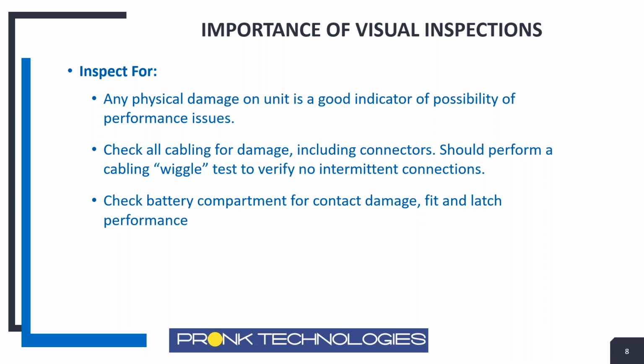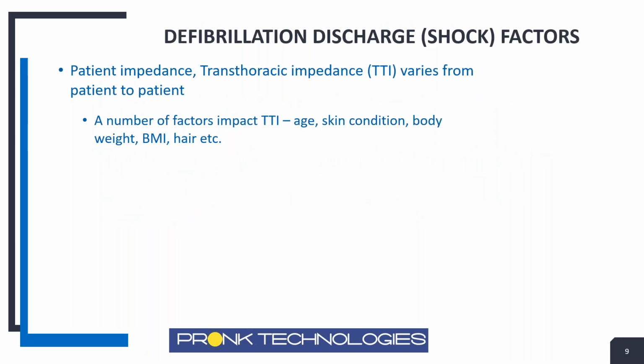It works once, but they would vibrate the unit a little bit and the battery would lose contact, the defibrillator would turn off, or the latches were damaged in some way, the battery wouldn't stay latched. So looking at that battery compartment is really, really critical for this as well. So when we're testing defibrillators, we need to do a variety of things. One of the most common and important tests is the discharge test, the shock test.